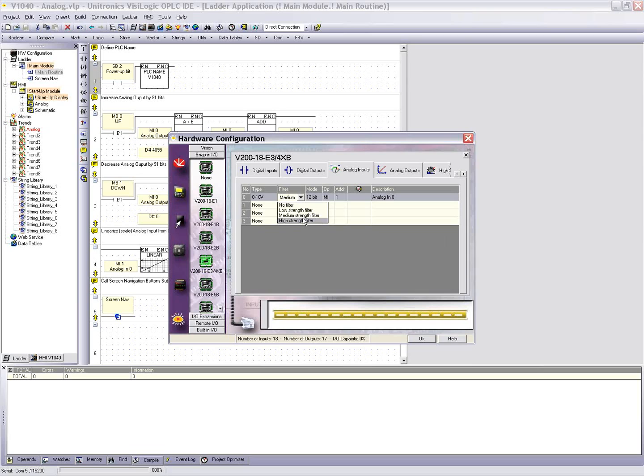I'll leave it on 0 to 10. You have the option of defining a filter as well: no filter, low strength, medium, or high. This is really doing is if you have a sensor that's fluctuating slightly, you can select the software filter here, which basically just takes the average of the last couple readings and calculates that average so you can eliminate any jittering input or slightly fluctuating value, just so it looks more presentable for any calculations or on the HMI screen.